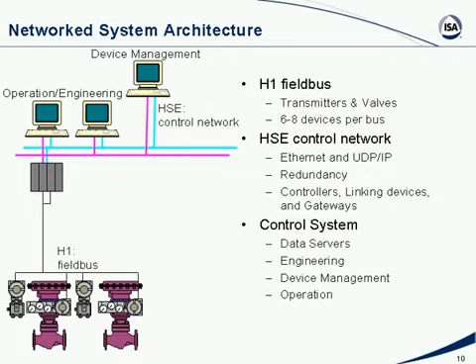All of the devices on the field bus have a common sense of time because they all have a clock in them, and these clocks are synchronized, okay? This is important for the scheduling I talked about, which is important for PID control, but it also allows all the alarms detected in the devices to be time-stamped, so we get essentially a sequence of event time-stamping at the source, okay? So it becomes more accurate. Okay? And firmware download is also another unique feature of Foundation Field Bus, actually.